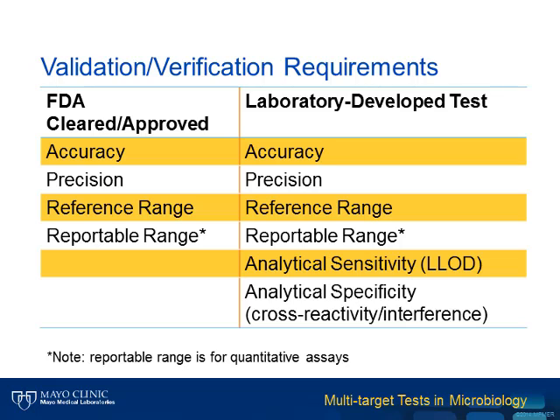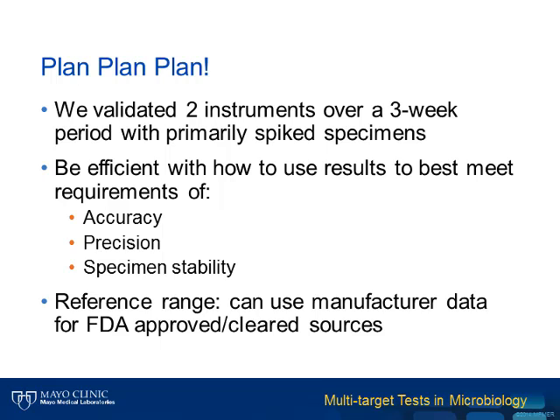I want to share our experience validating a respiratory pathogen panel. We validated two instruments over a three-week period with primarily spiked specimens. There are several companies making whole organism control material that can be used for quality control and for spiking in validation experiments. We found it helpful to be efficient in how we use results to best meet the requirements of accuracy, precision, and specimen stability testing. One specimen often was able to fulfill several of these criteria.